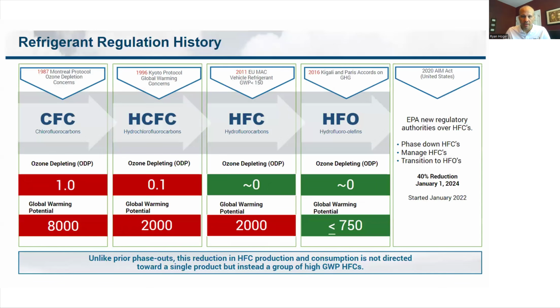All right, so on the background side of the equation, I will spare you the 2 hour lecture on refrigerant changes over time and why we're changing them, blah, blah, blah. The fact of the matter is that the current rules that we have to deal with in the United States require us to have the global warming potential down below 700. I know my slide says 750. That's because that was the most recent number, but that final number actually ended up being 700.